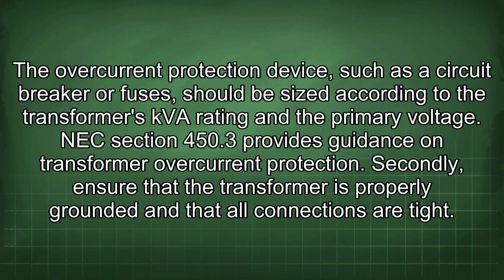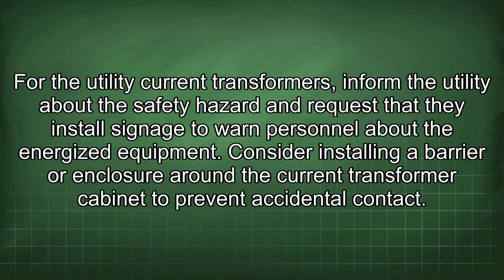The overcurrent protection device, such as a circuit breaker or fuses, should be sized according to the transformer's kVA rating and the primary voltage. NEC Section 450.3 provides guidance on transformer overcurrent protection. Secondly, ensure that the transformer is properly grounded and that all connections are tight. For the utility current transformers, inform the utility about the safety hazard and request that they install signage to warn personnel about the energized equipment.